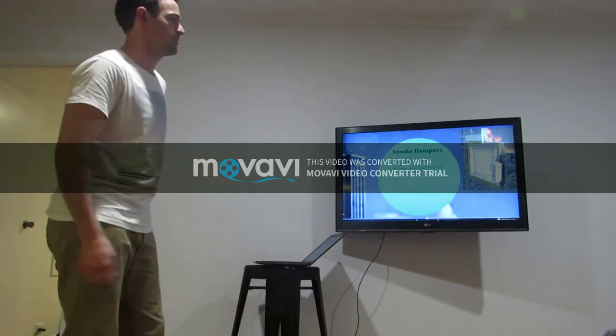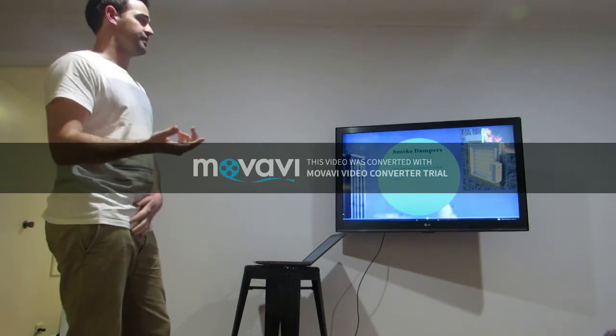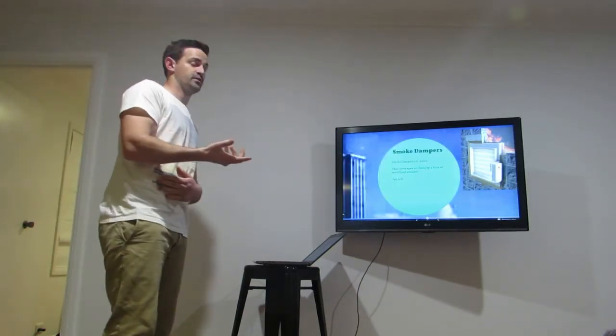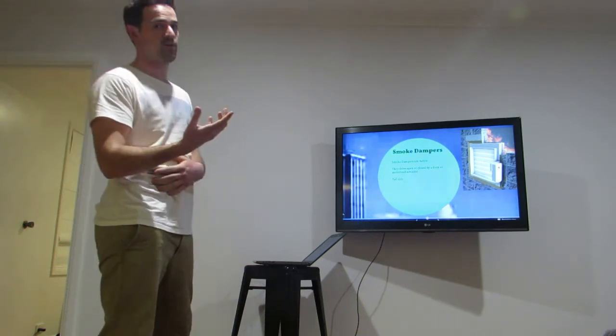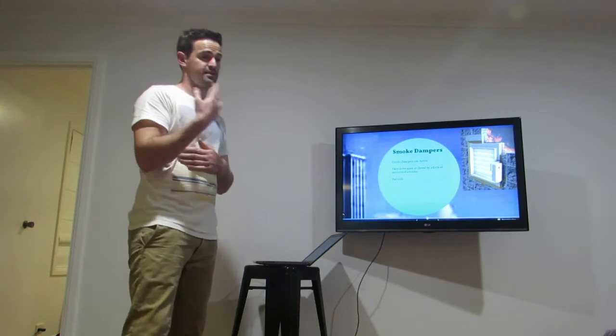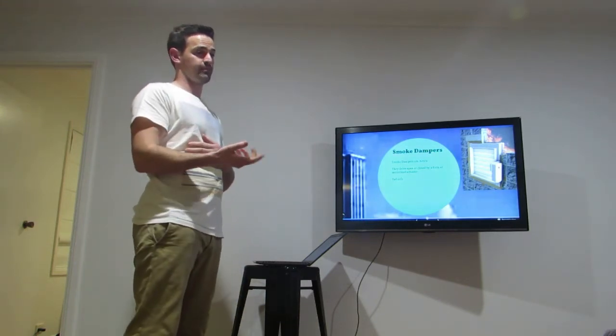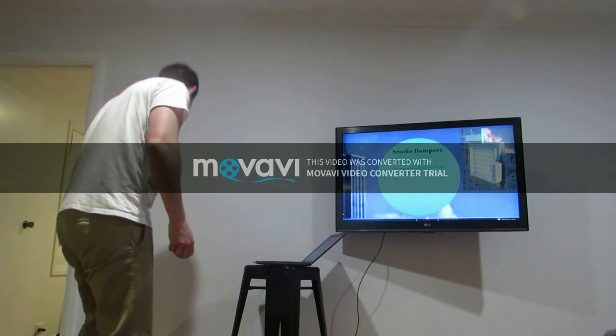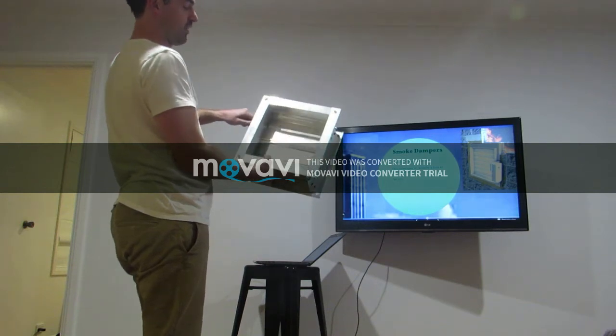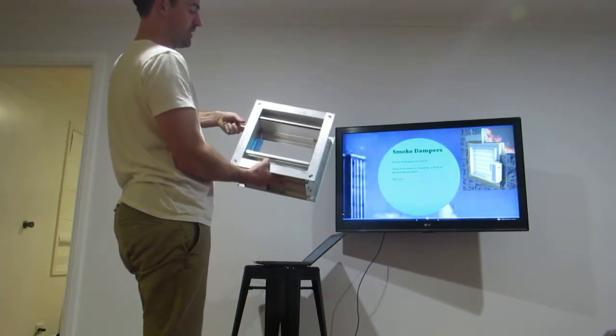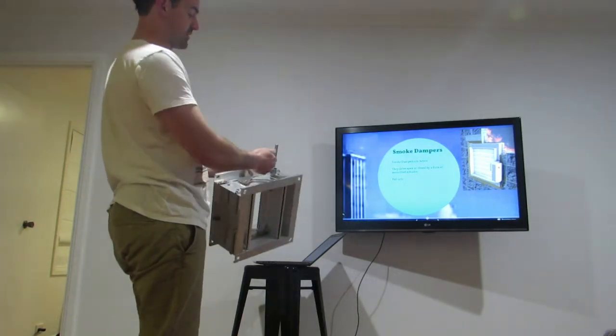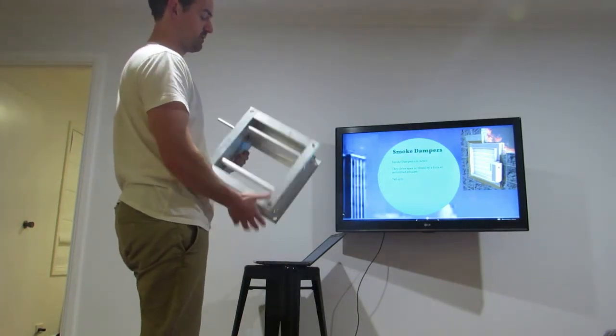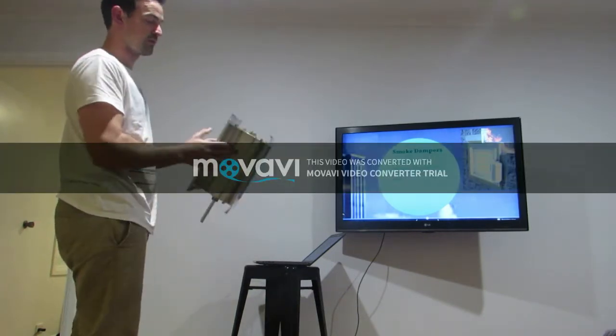Smoke dampers, these are active. Smoke dampers are driven by means of an actuator. They drive open and closed, and they need to be able to fail safe, meaning that if the motor or actuator loses power, supply air dampers spring closed and exhaust or spill air dampers spring open. Now I've got a damper here just to show you the quick movement of a fire damper. They'll close like that or drive open. We check for corrosion and the linkages, we check the actuator is fixed properly, and we make sure that the right damper is installed. We also check the wall around the damper as well.